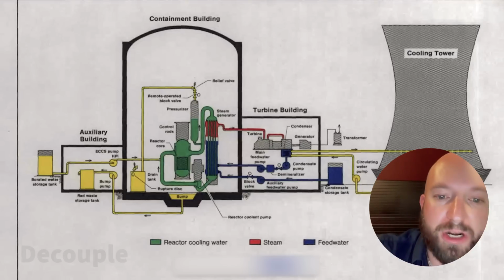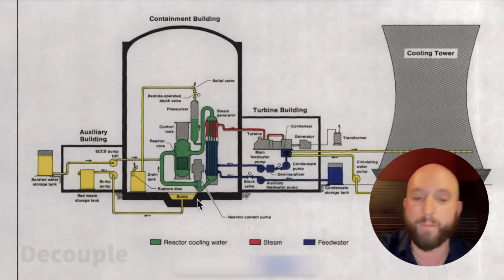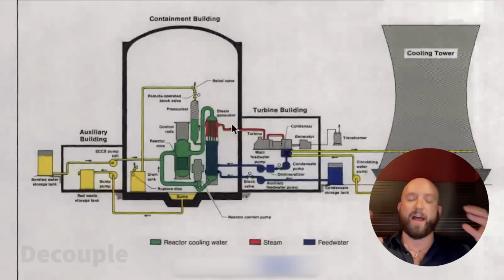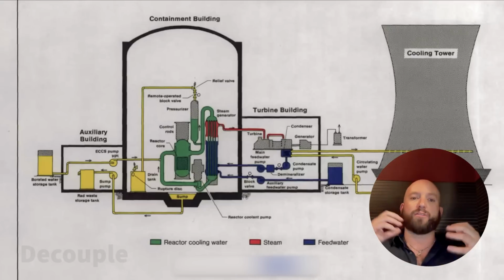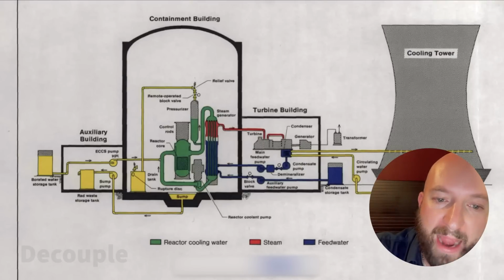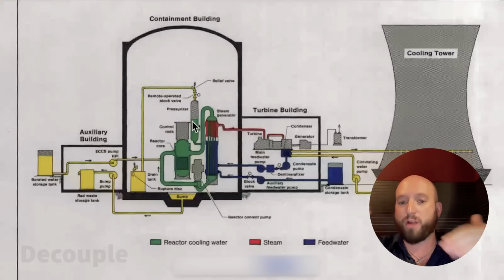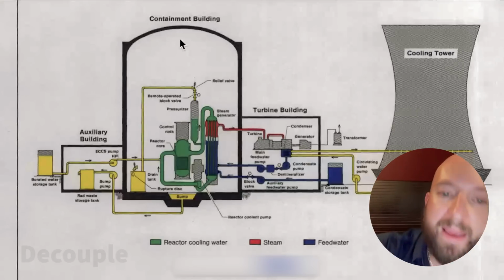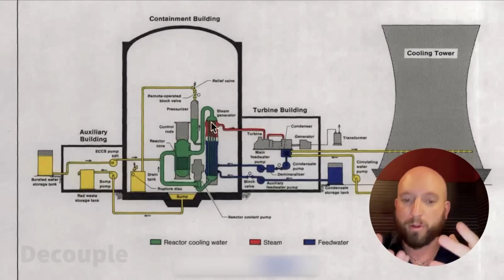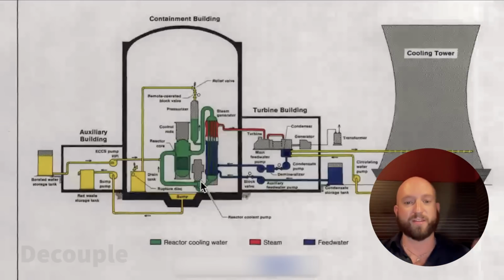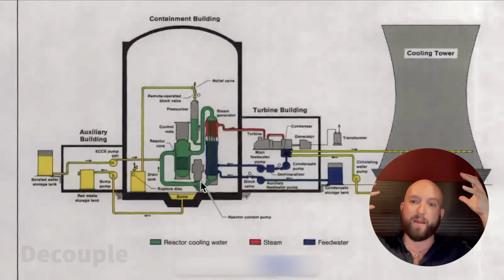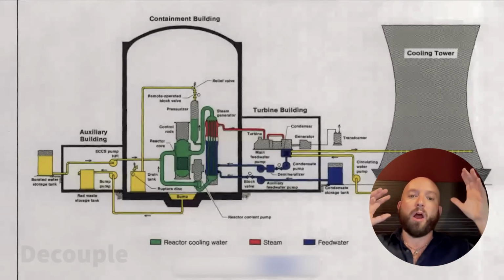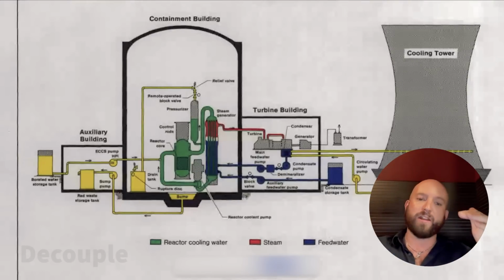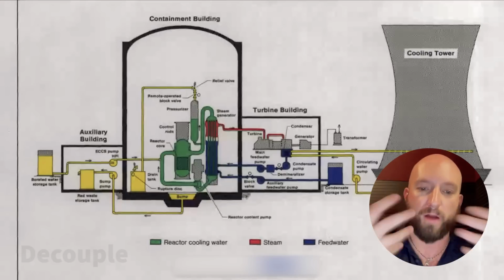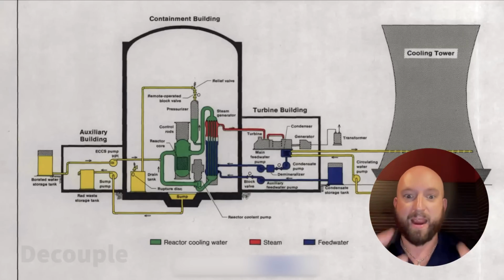And the reactor coolant pumps, which are still spinning and maintaining flow across the core, all of a sudden start vibrating violently. Because what's occurring here is the reactor coolant system, which is always supposed to be solid liquid water except for the pressurizer, is now depressurizing so rapidly that there's boiling going on in the RCS, which is causing massive bubbles of steam to accumulate in these massive pumps that are the size of 18-wheeler trucks, spinning with 9 megawatts of power each.